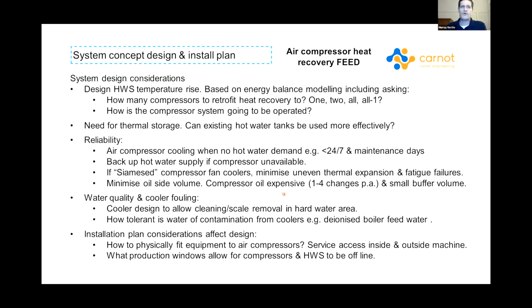We've talked about the water quality and cooler fouling. Stefan did as well. Are you designing for a hard water area, or are you designing for a soft water area? You will get scale build-up. A lot of compressor companies, the OEM systems, won't sell a system if it's going to be heating the water above 80 degrees because they're scared of scale build-up inside the machine. So you need to design your system. If you're going to get scale, how are you going to get rid of that scale and keep your system working properly? Or are you going to just replace the coolers? Are you going to try and clean the coolers? Are you going to do both coolers, one cooler? So there's a lot to consider in that respect.